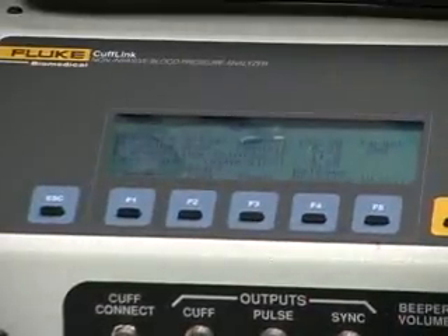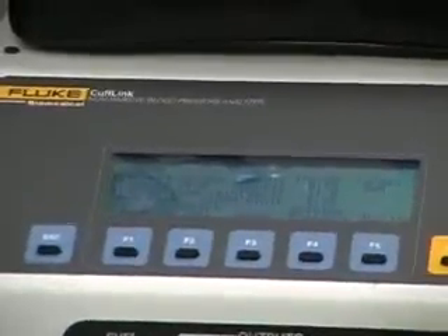Okay, so the 1 minute time has expired, and we're reading a leak rate of 5 millimeters of mercury. So with that, it's a matter of looking at the specification for the device as it's specified by the manufacturer for this device to see if it's acceptable. Yes, exactly.